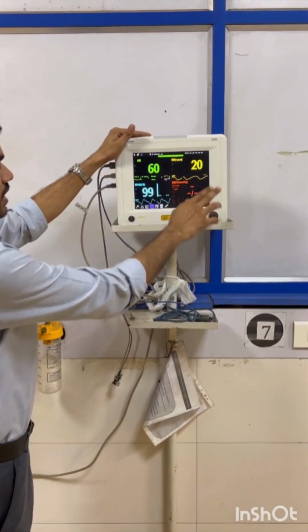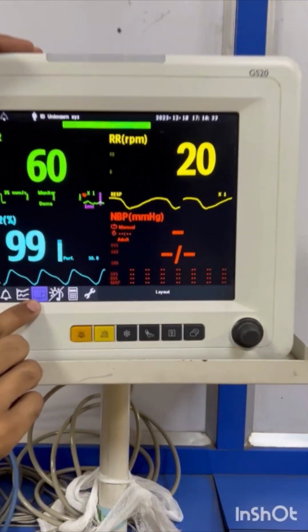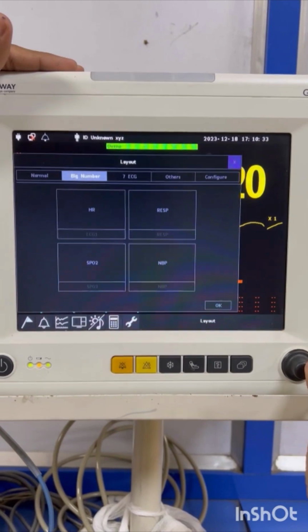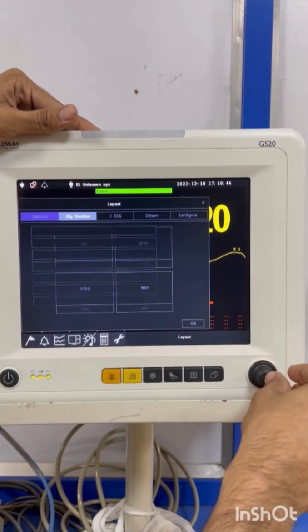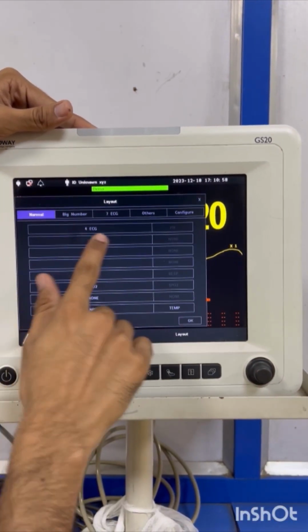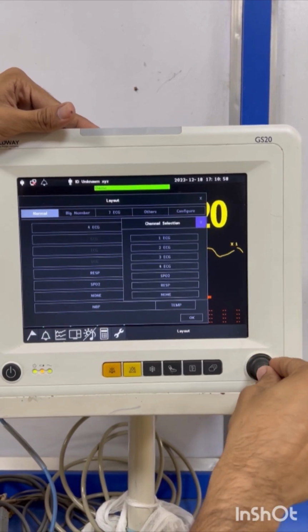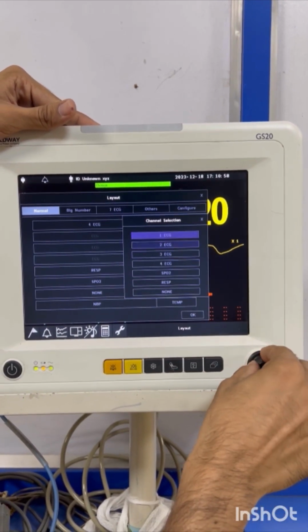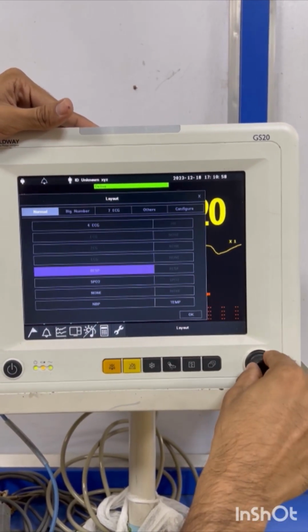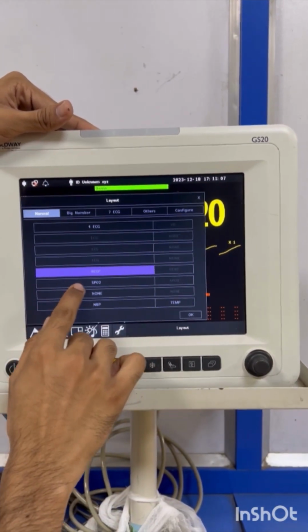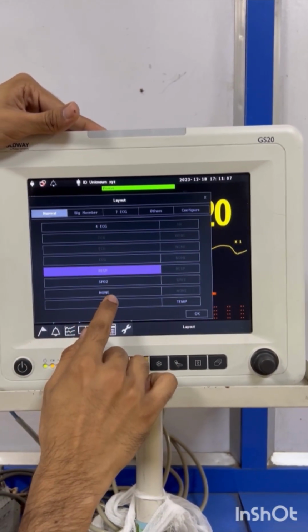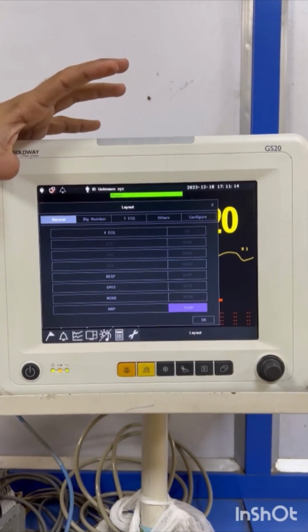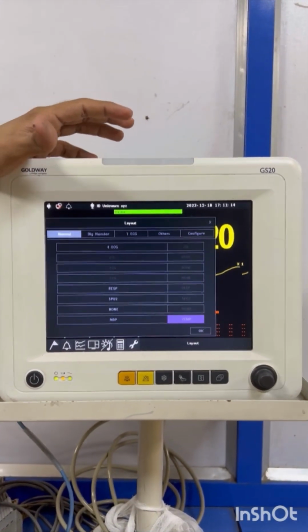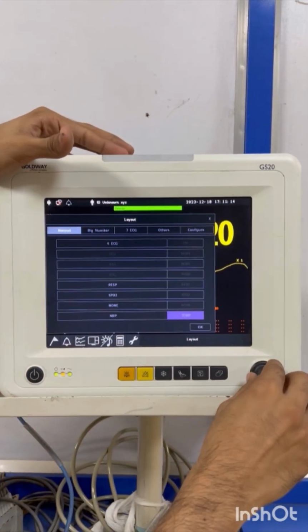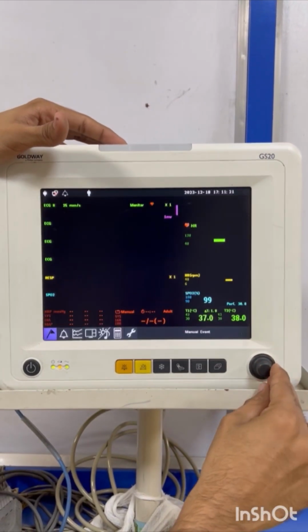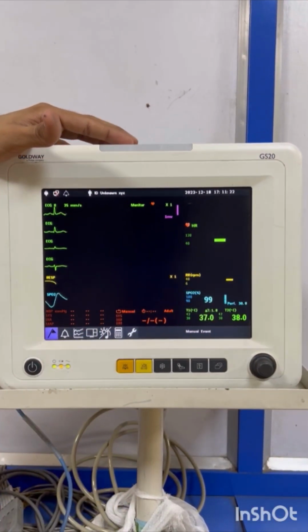To set the display layout, you have to go in this parameter. I'll select from rotary knob. In normal screen layout, you can choose how many leads, ECG leads you want to see. 3 lead, 4 lead, 5 lead. Then respiratory, SpO2. Here also you can add another parameter. According to your convenience, you can adjust these layouts and you just have to press OK. Then screen layout will get changed.